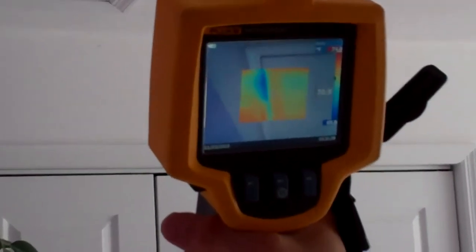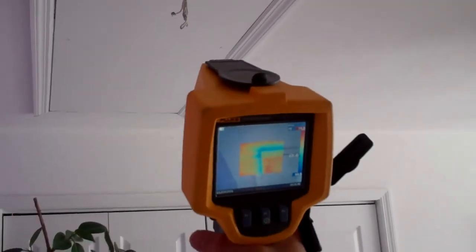Okay, you ready? Again with the thermal imaging gun, we went to the attic access, and this is a drop down stair. And you can see we were talking about weather stripping there. Look, perfect. We have the blower door on, and what's happening is that you can see that cool air coming in from the attic, coming into conditioned space, and this just shows via thermal imaging some of the leakage that is going on.